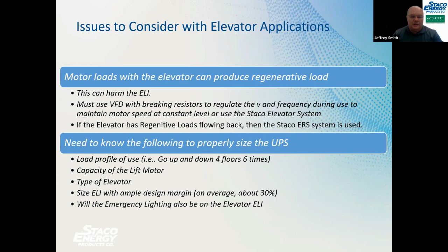So potential regenerative power, that's what we have to look at for concerns. We have to get rid of that. We have to remember to look at elevator, the lighting, any type of fans, load bank, and a design margin so you can make sure you have that to be able to run as long as what's required locally.